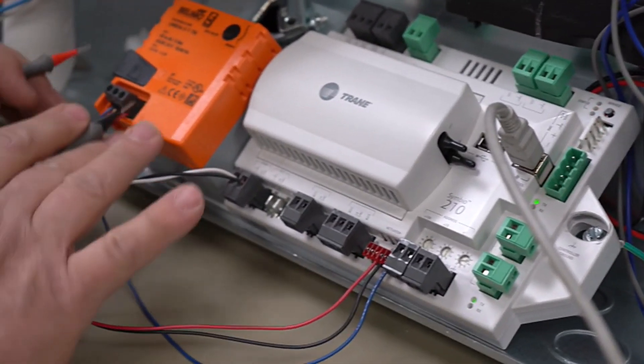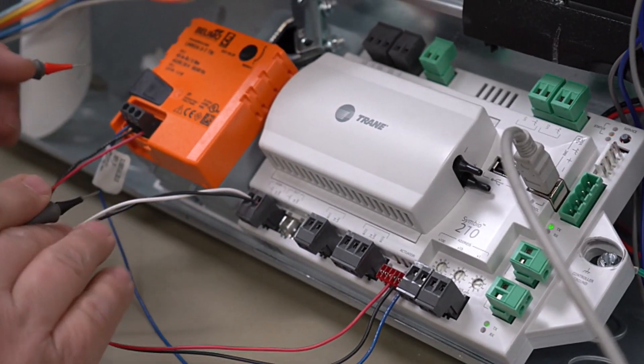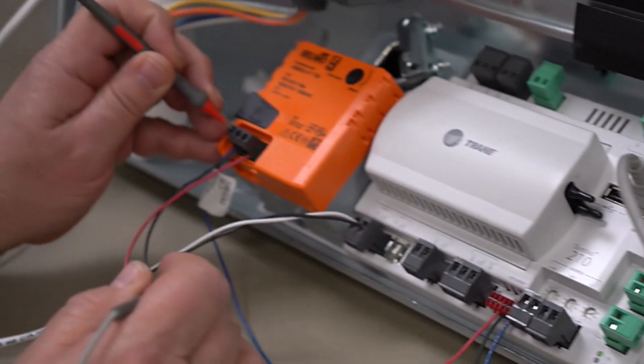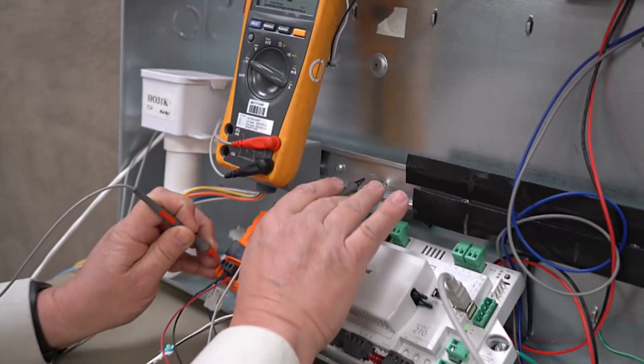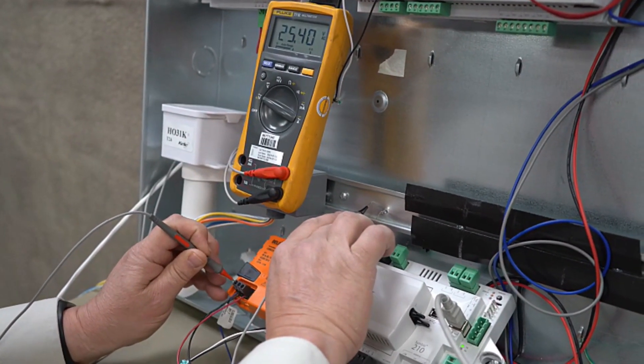So this blue wire here, we're going to measure all our voltages over here at the actuator just for ease of operation here. So if we look on that blue wire, that's our hot leg. So there's our 24 volts going to our actuator.